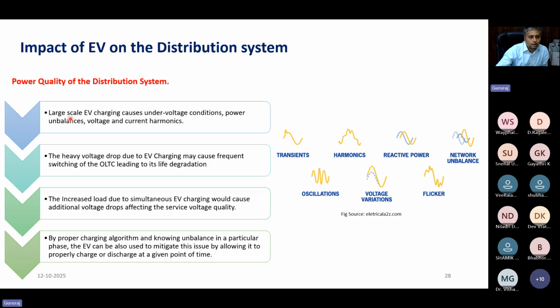Okay, large scale EV charging causes under voltage conditions, power imbalances, voltage and current harmonics. Heavy voltage drop due to EV charging may cause frequent switching of the OLTC, leading to its life degradation. This is an important issue. Many of the countries today are speaking about solid state transformers, SST. So if you have an SST in the system, probably you're not worried much about the tap changing issues.